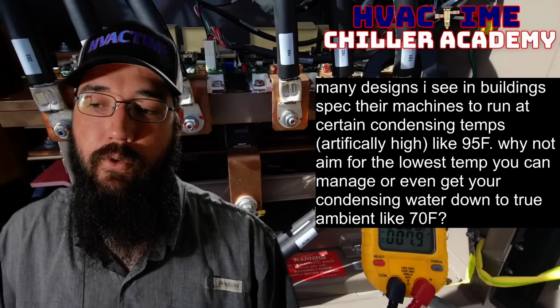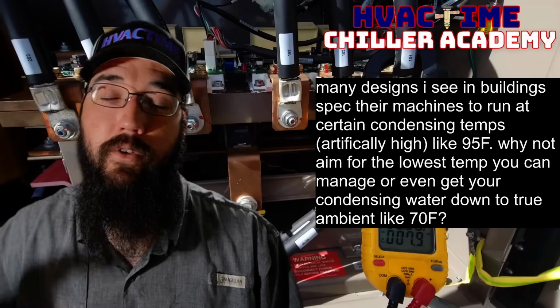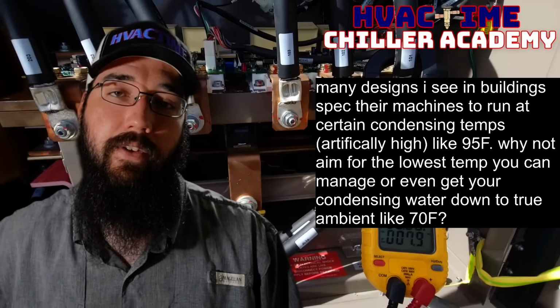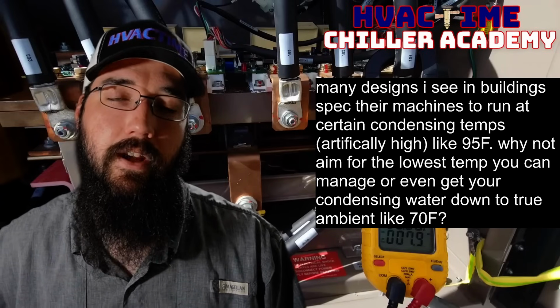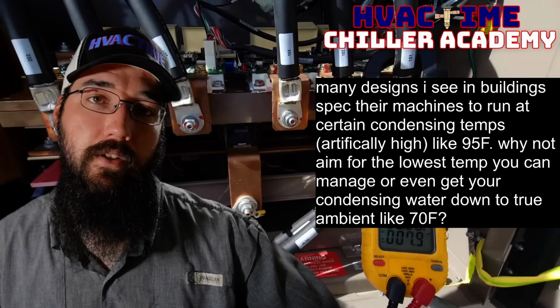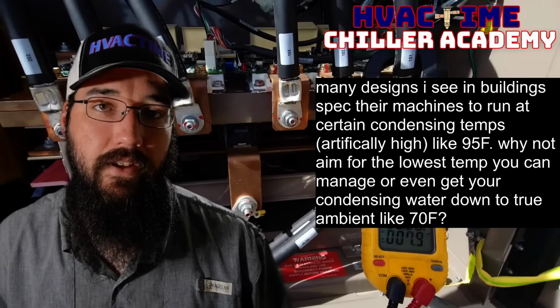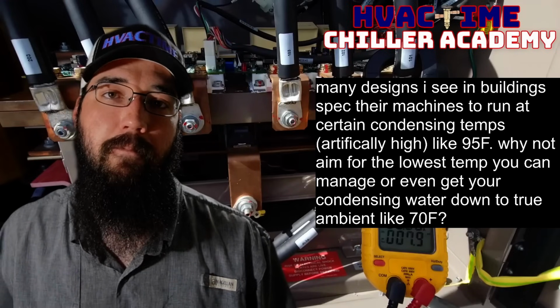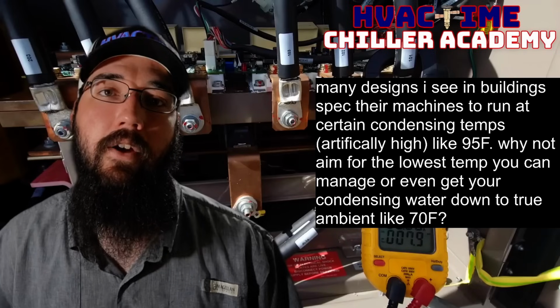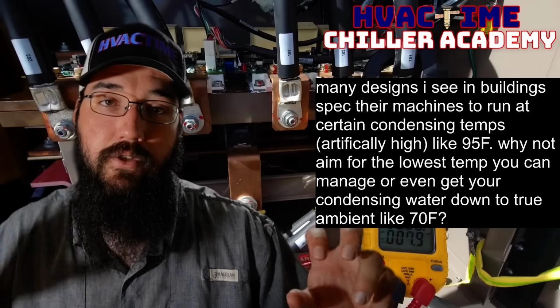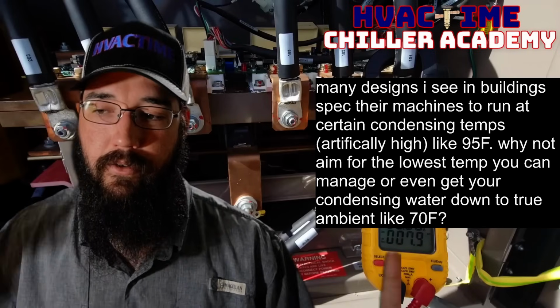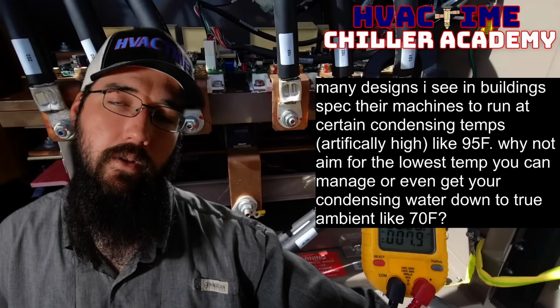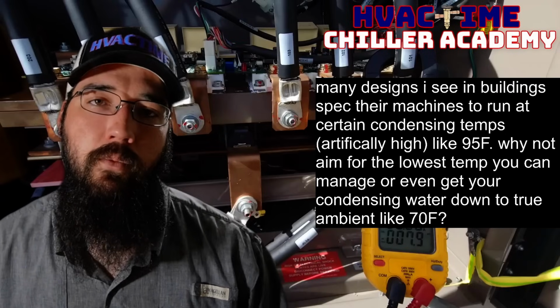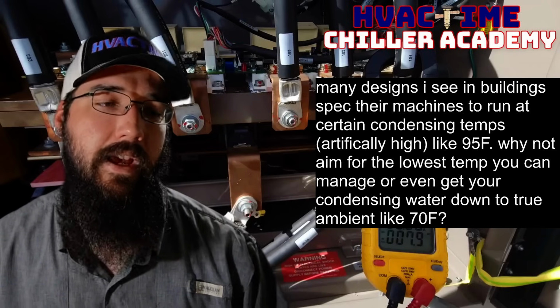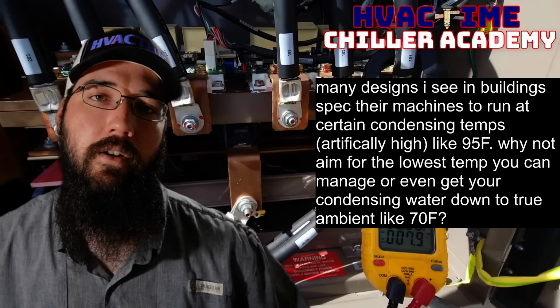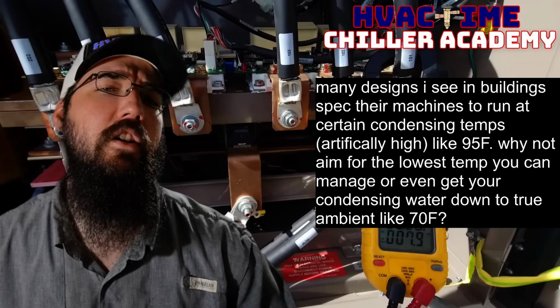Part of what they do is they'll lower the static set points on these buildings. That's something they'll do at the air handler levels, right? More than just try to get the condenser fan or the cooling tower fans to stage down. They'll also go as far as running super low statics on all of the air handlers so that they can slow down the air handler motors and, again, achieve Energy Star ratings and all the other jazz that they go for. And so a building that needs to run 1.2 inches of static for smooth operation, they'll turn around and drop it to 0.8 and say, oh, it'll be good enough.